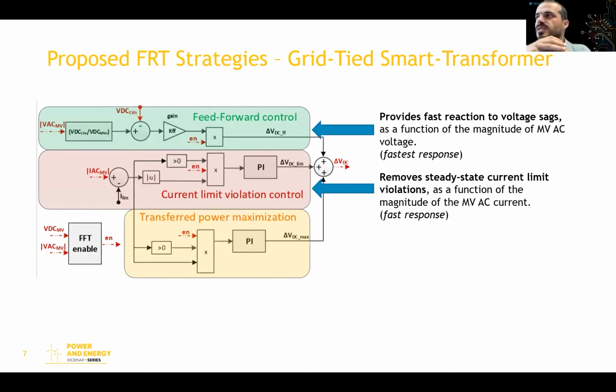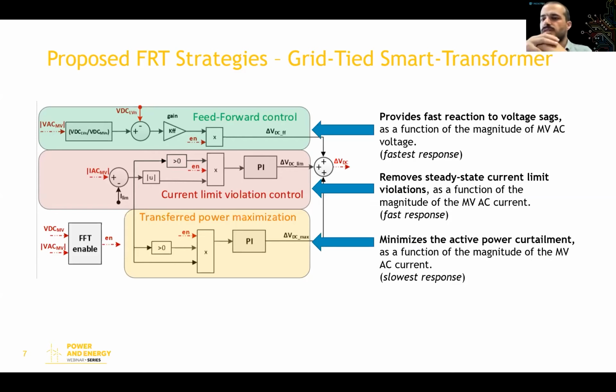Then we need to remove the steady state current error to ensure that the current limits of the medium voltage inverter are respected. And because we need to optimize the power transfers, since sometimes the power curtailment may be superior to what is really needed, we have this third element which maximizes that, so that we only curtail the power that we really need to curtail.